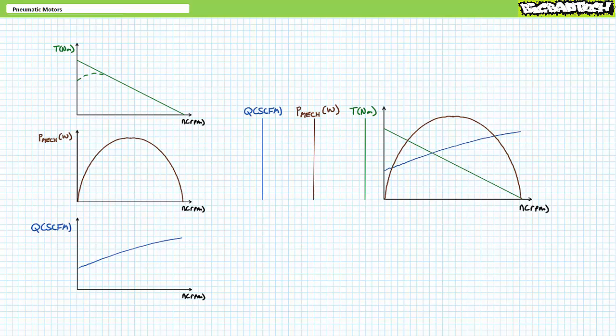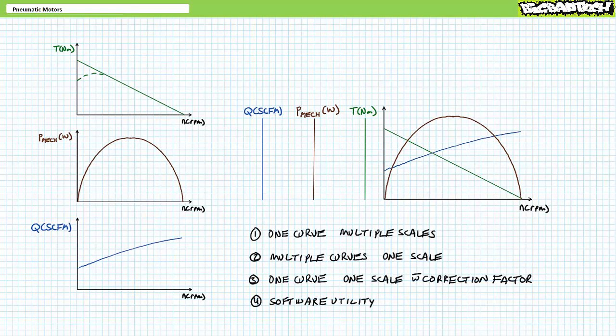We can use this type of chart to determine the motor's operating point—a condition with a known speed, torque, flow rate, and mechanical power. But what about pressure? There are several ways air motor manufacturers account for load-induced pressure, a majority of which are awful and bordering on the unworkable. Method one uses one curve and multiple scales. Method two uses one scale and multiple curves. Method three uses one curve, one scale, and a correction factor table. And lastly, method four uses the internet or manufacturer computer application.